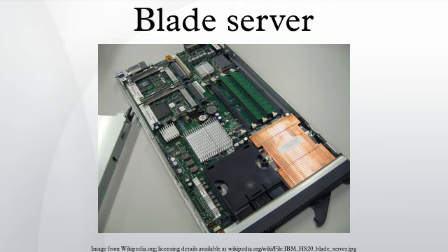The blade's shared power and cooling means that it does not generate as much heat as traditional servers. Newer blade enclosures feature variable speed fans and control logic, or even liquid cooling systems that adjust to meet the system's cooling requirements. At the same time, the increased density of blade server configurations can still result in higher overall demands for cooling with racks populated at over 50% full. This is especially true with early generation blades.